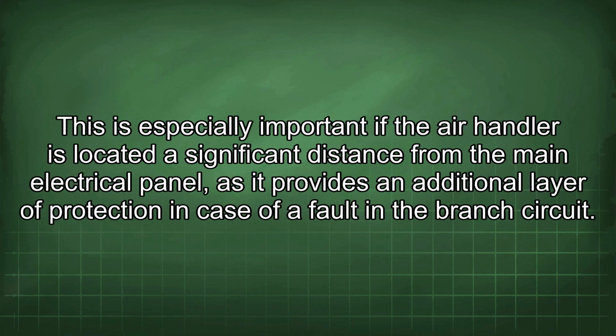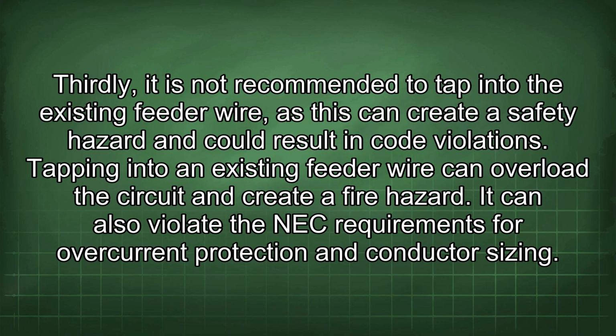This is especially important if the air handler is located a significant distance from the main electrical panel, as it provides an additional layer of protection in case of a fault in the branch circuit. Thirdly, it is not recommended to tap into the existing feeder wire, as this can create a safety hazard and could result in code violations. Tapping into an existing feeder wire can overload the circuit and create a fire hazard. It can also violate the NEC requirements for overcurrent protection and conductor sizing.